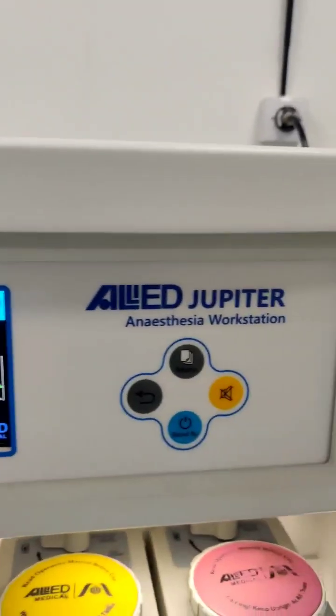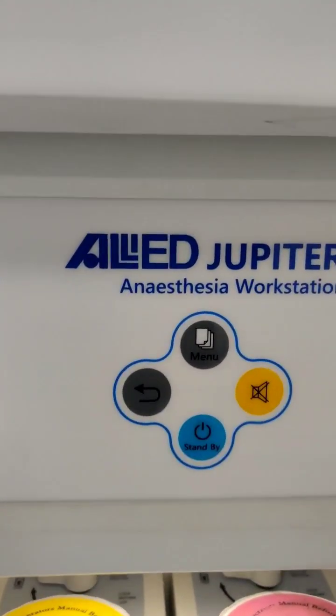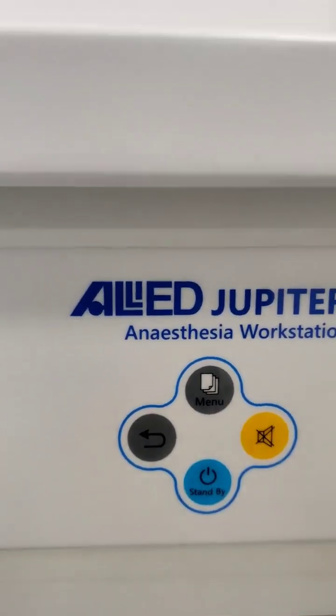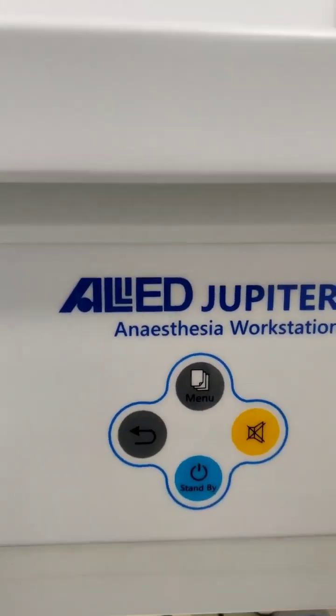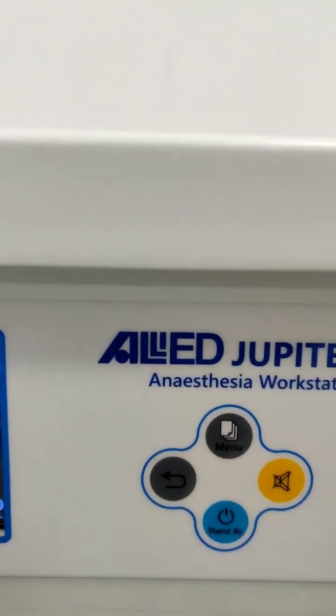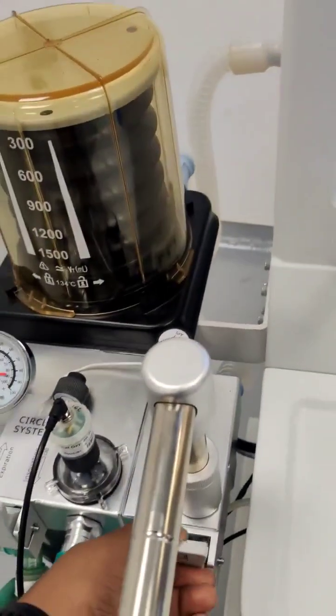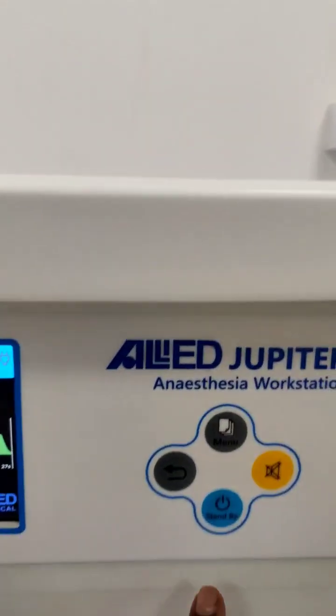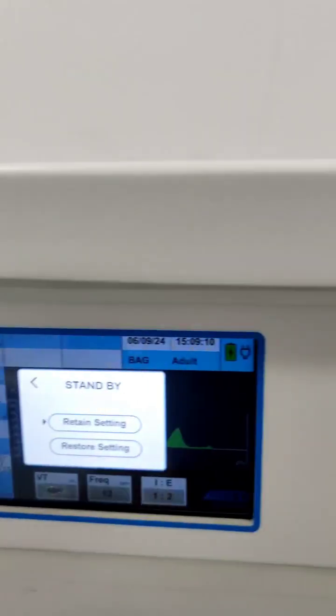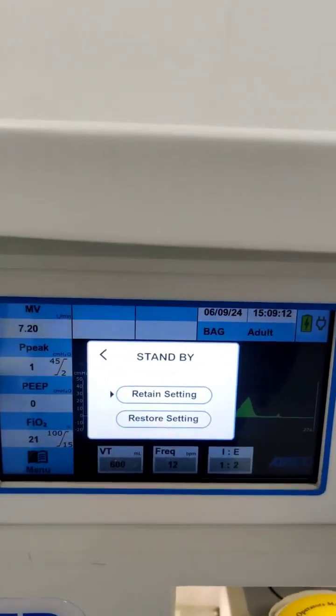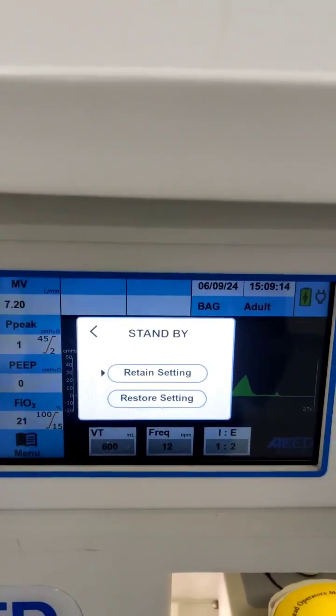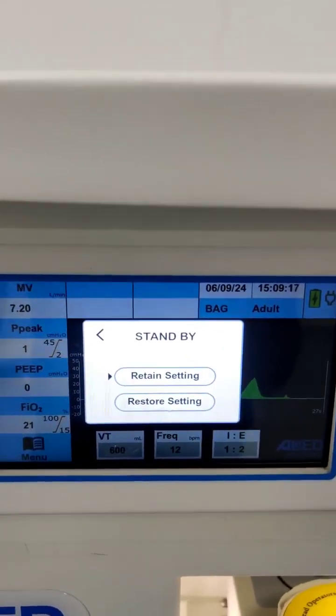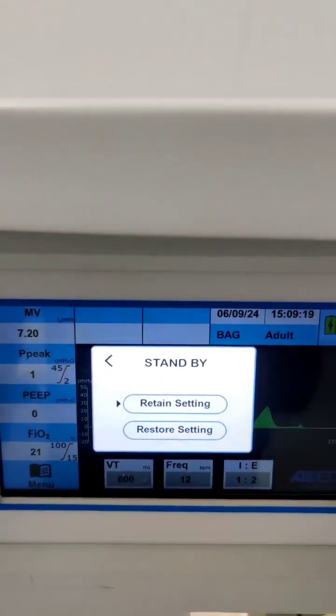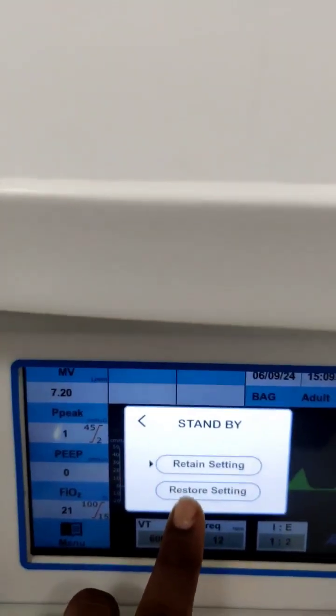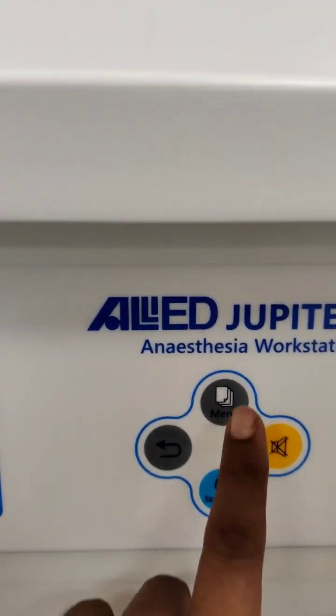Coming on to the buttons or the keypad which we are giving. The menu button will be deactivated when the machine is operating. For using the menu button, you have to first put the machine into standby mode. This is the standby key. As soon as you press the standby key, you will get two options: you can retain the previous settings, or you can restore the settings to the default settings. If I select restore settings, it will go to the default values. And now you can go into the menu.